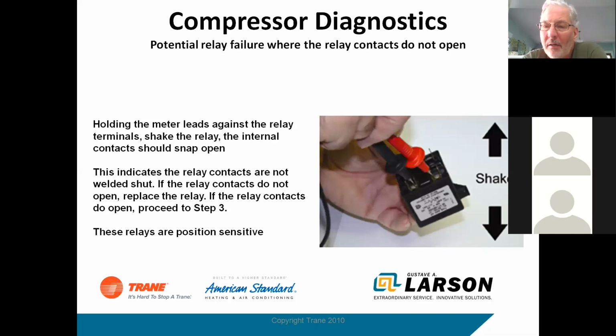Okay, and by the way, these are position sensitive relays. You can't put them sideways or upside down. They depend on gravity to hold that contactor closed. And as they energize, the coil picks up and opens that contact. So if you grab the unit and put your leads on terminal 1 and 2 and just shake that unit a little bit, the contact should open. Okay, and if it shakes and you can hear something moving in there, that means that the solenoid is free and the contactor is probably okay, or the start relay is probably okay at that point.